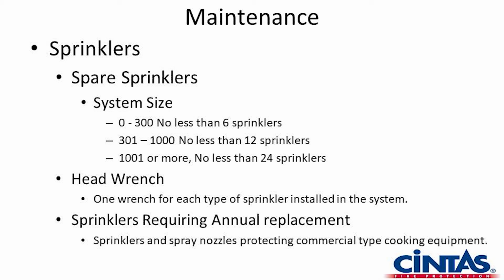They're there so that the correct sprinkler, and we've just talked about the characteristics of a sprinkler when we replace, should be like for like. So with 4 types of sprinklers, less than 300, I'm actually looking for 8 sprinklers, not 6. And it says 300 to 1,000 is 12, 1,000 or more, 24. That's what we're looking for. We're looking for 2 replacement sprinklers for each type in the building.